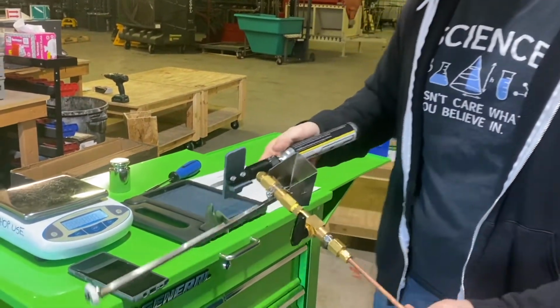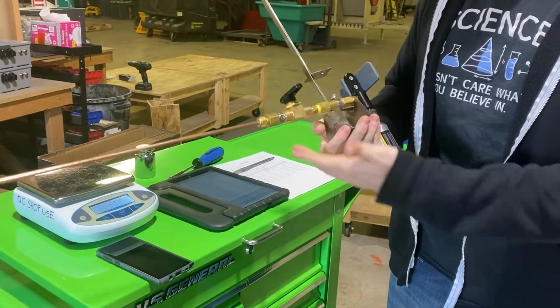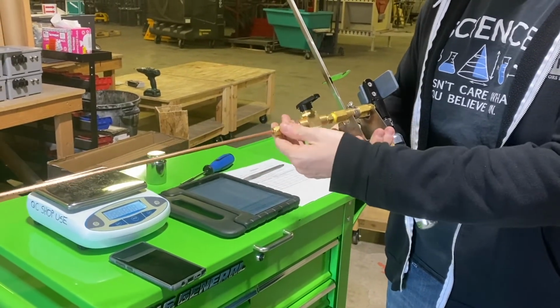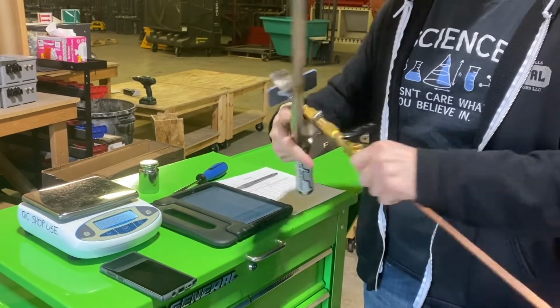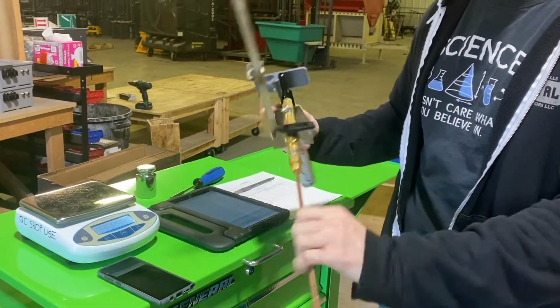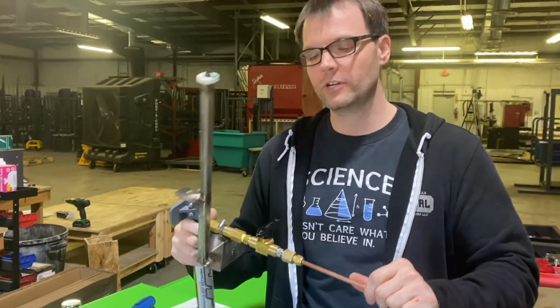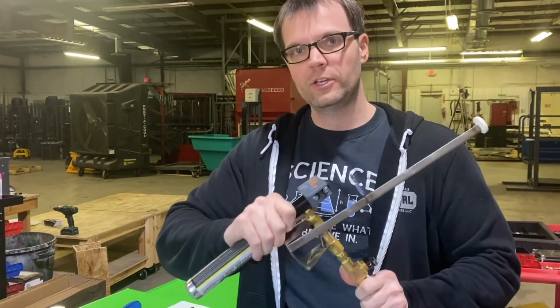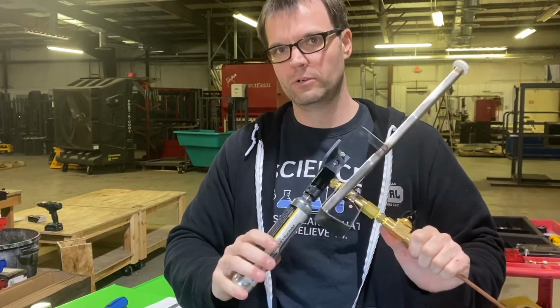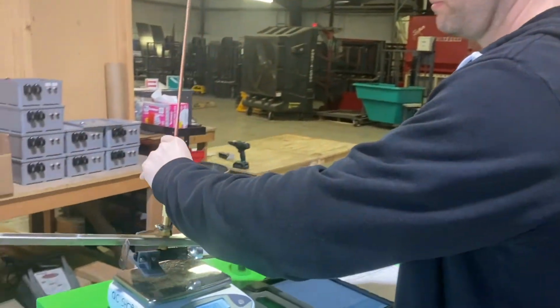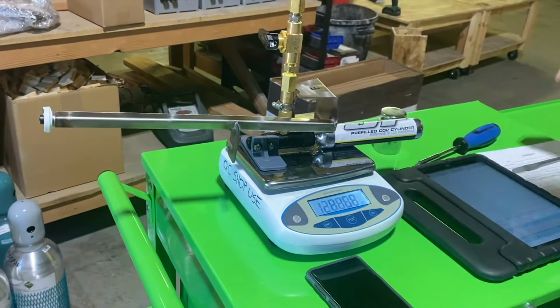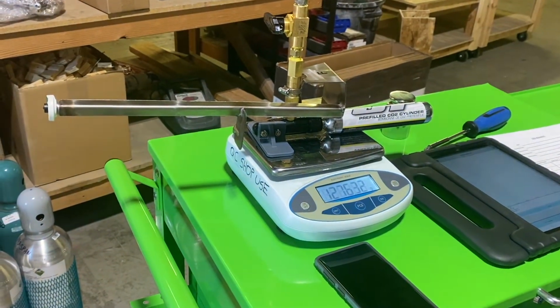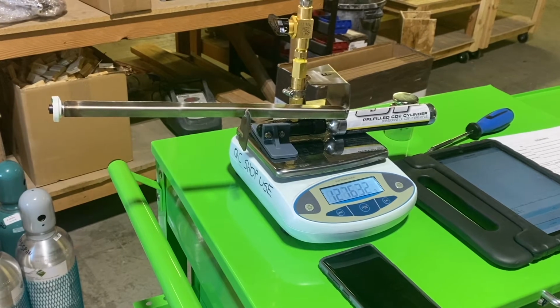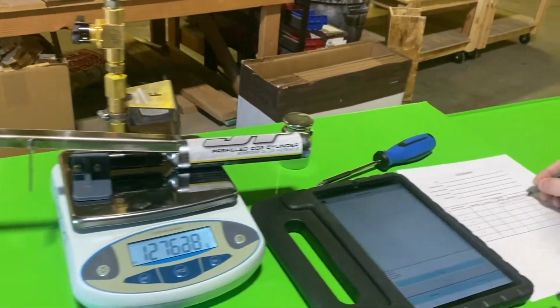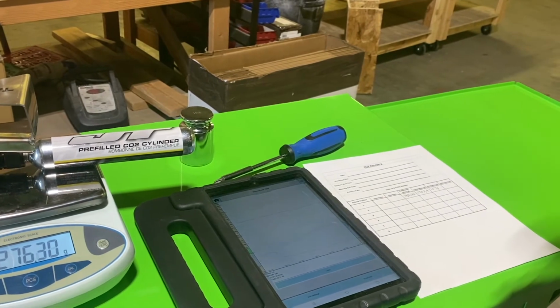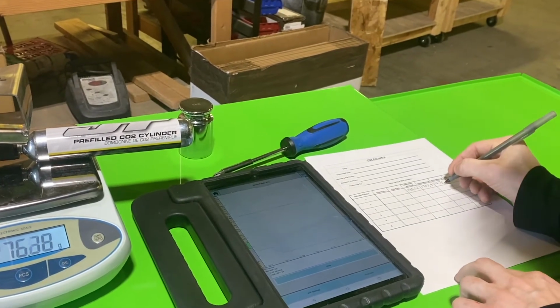So in the event that you do have very cold environments, you might notice frost or just condensation form all over the tank and the release device. So we want to make sure not to weigh that condensation or ice. So if you do have ice forming on here, make sure to wipe it down, make sure there's no ice or condensation on it when you weigh the system. So now we're seeing 1276.3.